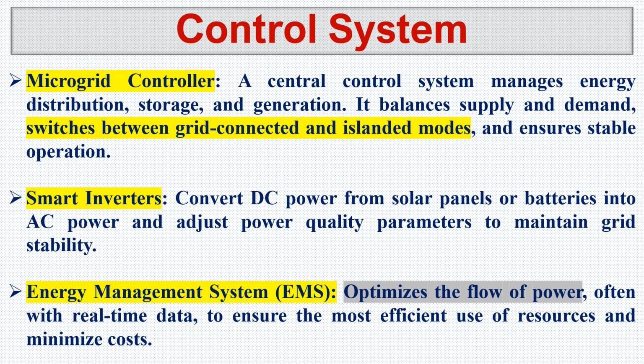Then we have the energy management system, which optimizes the flow of power in real time, making sure we optimize the cost. We don't want to waste money by generating more electricity than needed. Essentially, the energy management system makes sure that with minimal cost we are satisfying the local demand. If our generation cost exceeds the grid's energy cost per kilowatt hour, sometimes instead of generating we will buy from the grid.